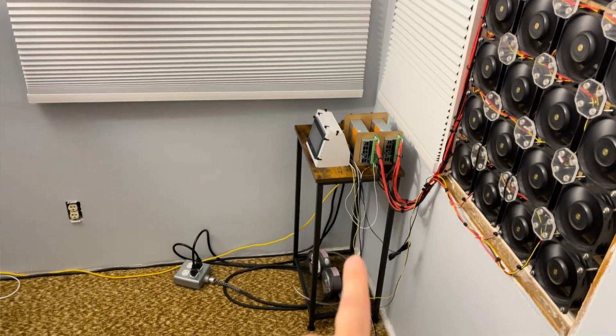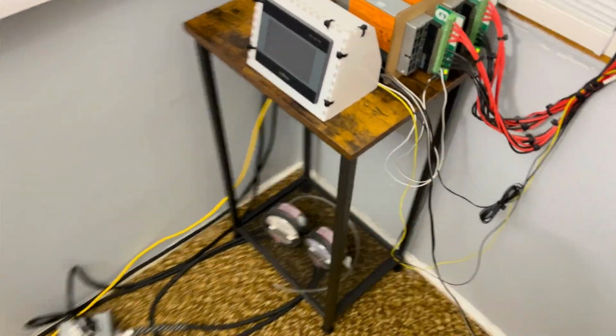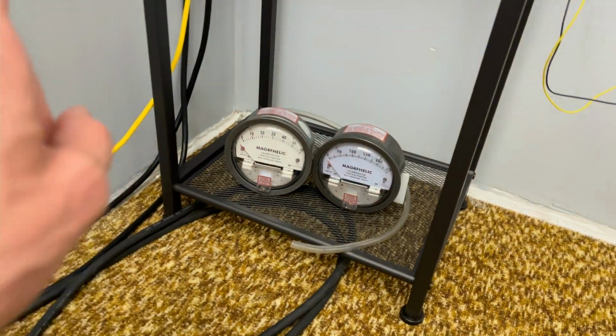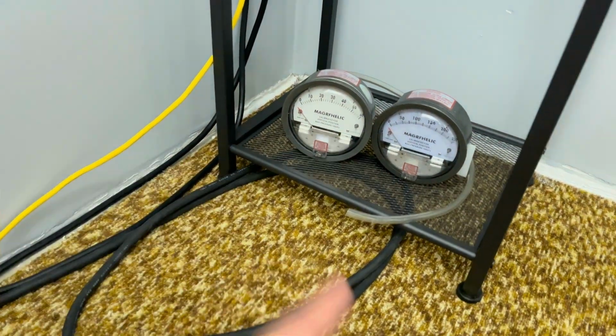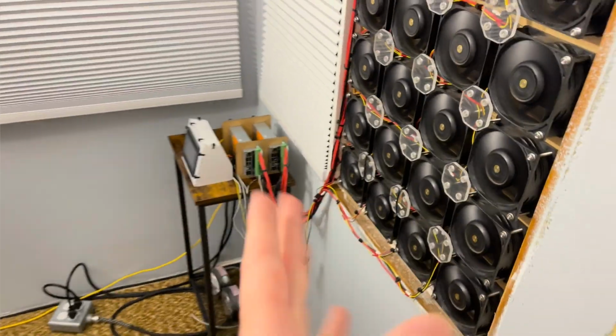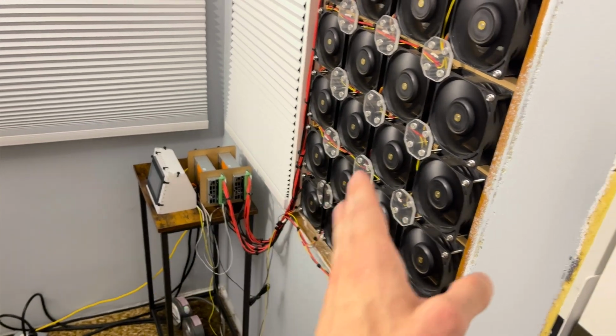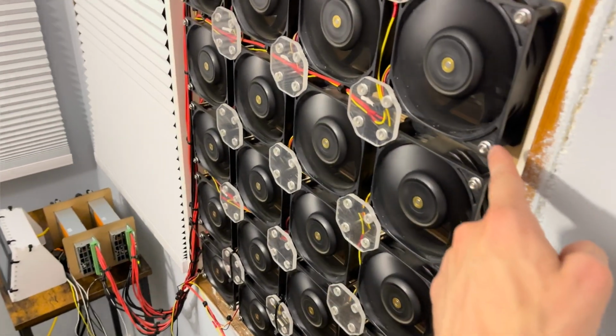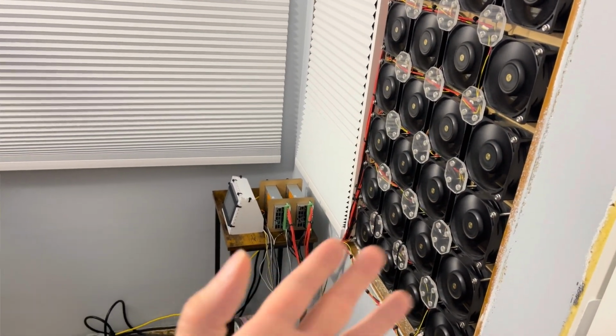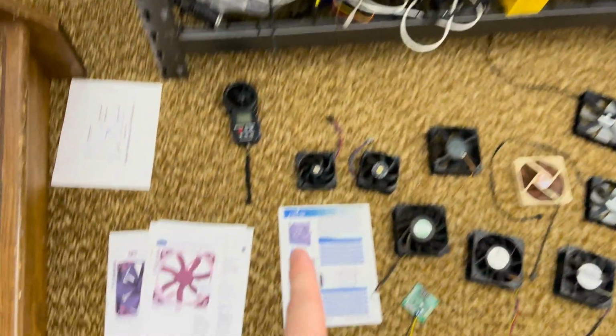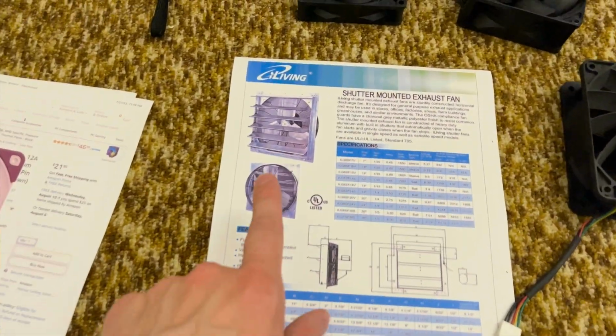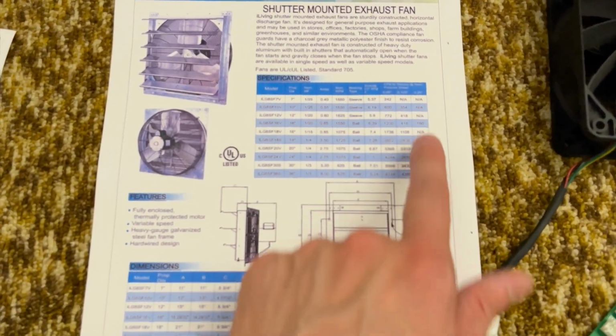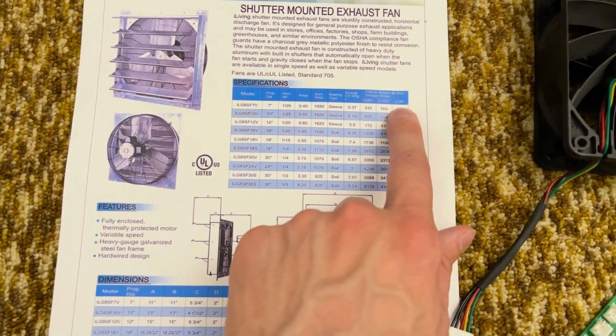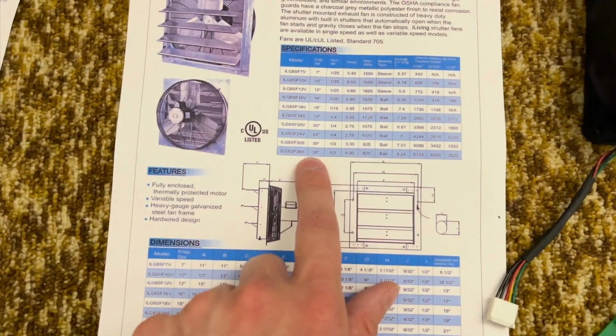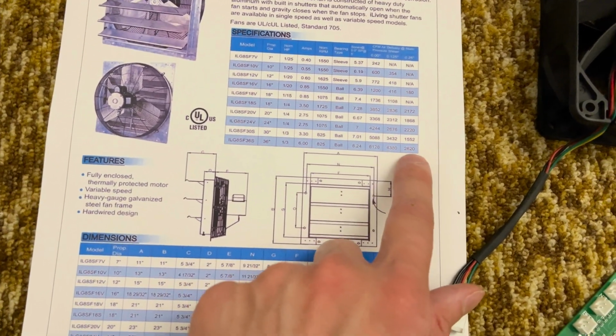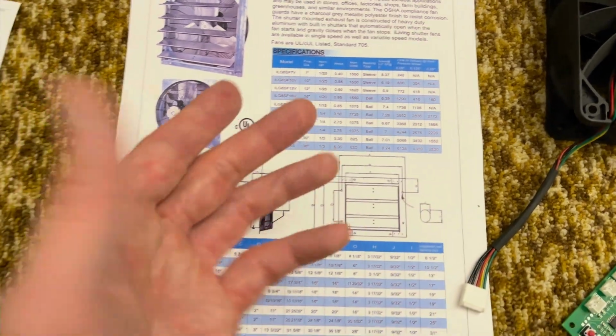I measured around 48 pascals from inside to outside using one of these, a differential pressure meter. Stick the tube outside, the other port is inside, tells you the pressure drop, right? So it says that this building is being depressurized at around 48 pascals, and these are full bore. Estimating there's going to be some pressure drop on the other side too that these fans will face. Probably around total 60 pascals, which coincidentally is right around a quarter inch of water column. So in my environment, this fan at around 6,000 CFM would be facing around a quarter inch water column of static pressure. So that means this big 36 inch fan, they say it's 6,000 CFM, I'd be getting closer to this number, 2,600. So that's an issue.